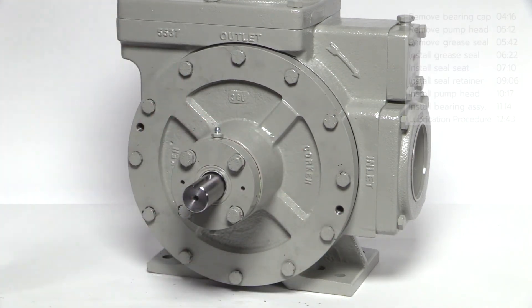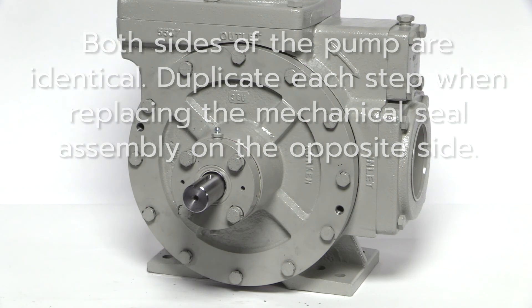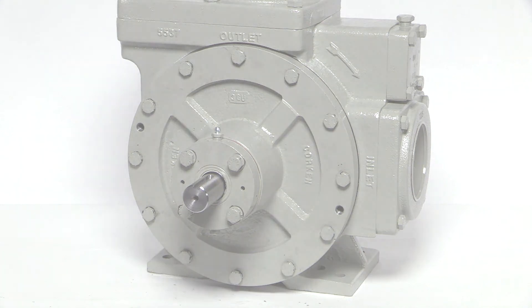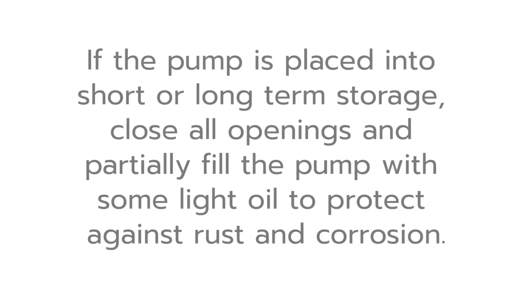Please note, both sides of the pump are identical, so duplicate each step when replacing the mechanical seal assembly on the opposite side. This completes the procedure for replacing a mechanical seal in all of Corken's Z-Series sliding vane pumps. If the pump is going back into service, slowly pressurize with vapor — this can be accomplished by slowly opening the bypass return line on most systems.